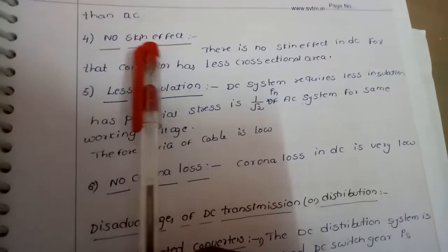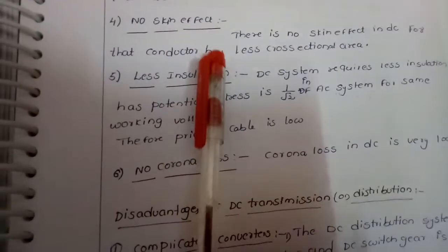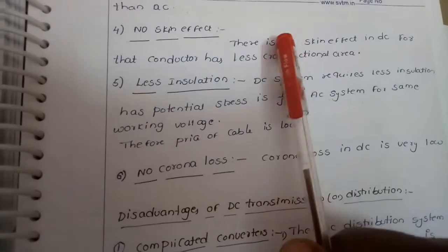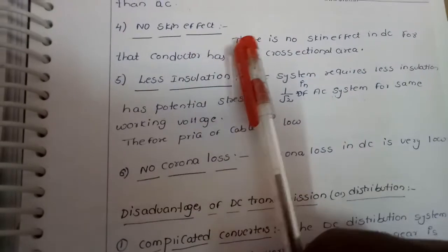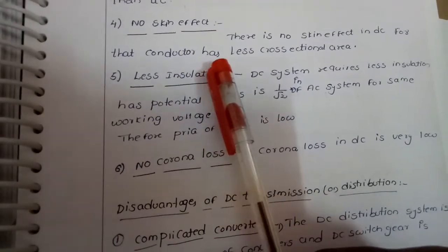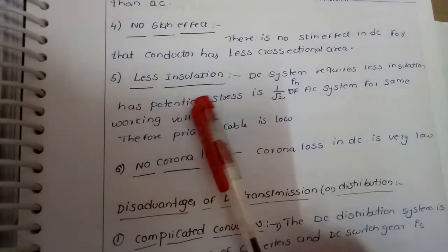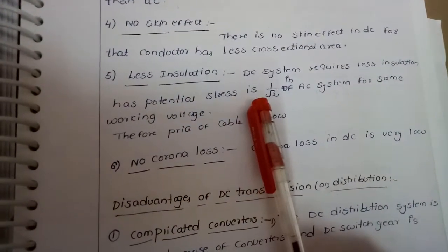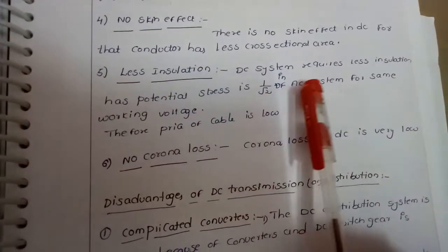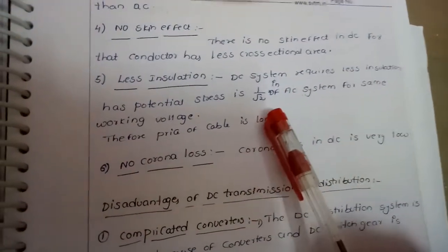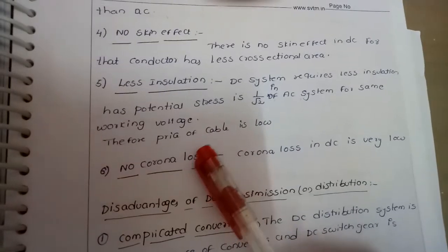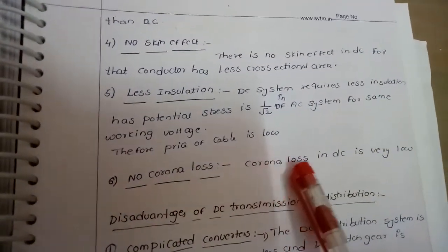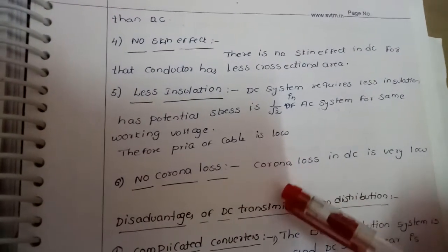Another advantage of DC distribution is no skin effect, meaning the conductor is fully utilized. Less insulation is required for DC systems because of less potential stress — the potential stress in AC is 1 by root 2 for the same working voltage, so DC cables are cheaper. There is also no corona loss in DC systems.